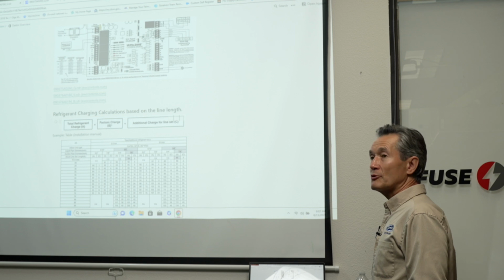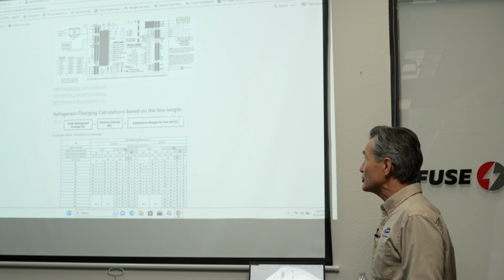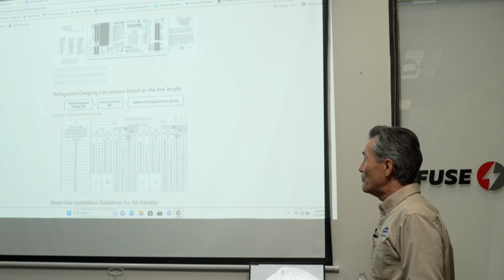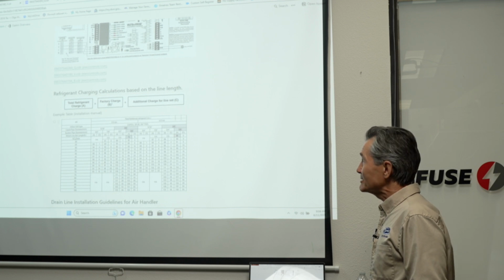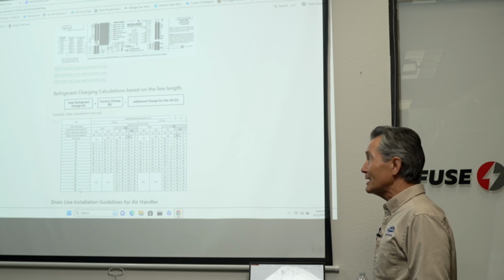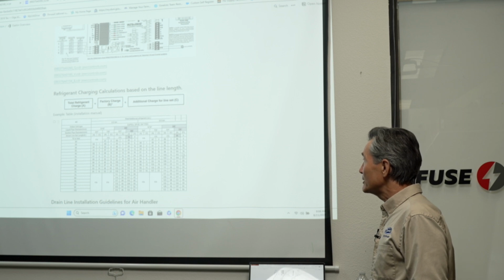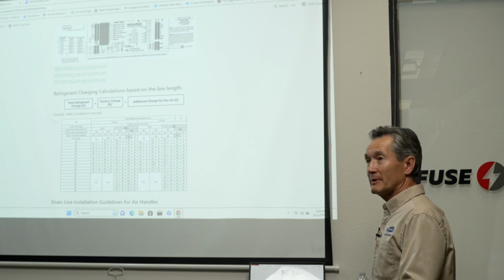Refrigerant charge - we mentioned this from the beginning. It's a simple calculation: total charge equals factory charge. It's pre-charged from the factory, and you have to calculate based on this table and the length of your line set. You should find the proper volume, and it should be charged in liquid form to the liquid side, to the low side, to the lower line size.